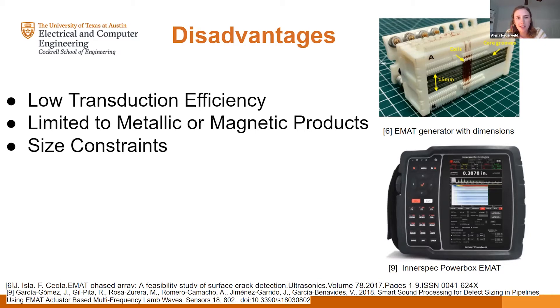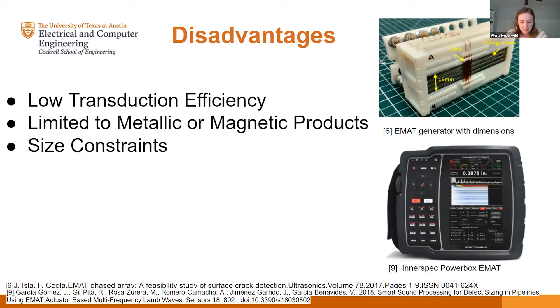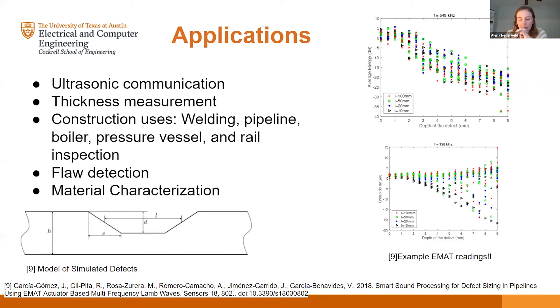EMATs are also limited to metallic or magnetic products. Using these non-destructive techniques on ceramics or plastics just doesn't work, or if it does the signal is so weak it's not worth using — you really should be using a piezoelectric in those cases. The last notable limitation is size: EMATs are much bigger than piezoelectrics. Small-scale EMATs are being worked on, but a lot of what makes EMATs great is lost when you make them really small, so that's definitely an area that needs improvement.